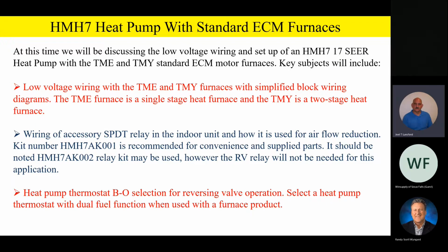Now, it should be noted the heat pump thermostat is still going to have that BO selection for reversing valve operation. And you're going to want to select a heat pump thermostat with dual fuel function whenever you use it with a furnace product. And let me stress that again: all the dual fuel function, if you have this on a furnace with the heat pump outside, is going to be at the thermostat level. So the thermostat's going to have to be able to sense outdoor air temperature to figure out its balance point and switch over point and all that kind of stuff. So be sure and select a heat pump thermostat with dual fuel function if you're going to be using it with a furnace product.